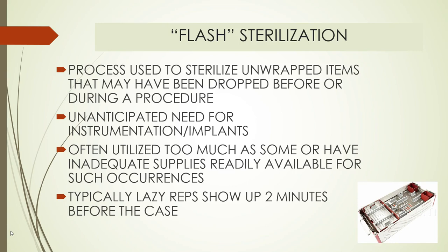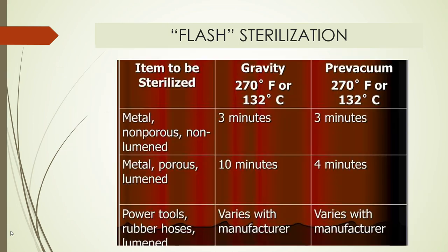It should not be utilized as a first choice elective technique in deference to having adequate supply of instrumentation. And a common example is a case we have scheduled, and the rep from the orthopedic company shows up right before the case and says, "Gee, doc, sorry I'm late, but don't worry, we'll go ahead and flash sterilize the instrumentation." The guidelines for flash sterilization are listed here, and for some power equipment, the time depends on the nature of the equipment and the composition of that equipment.